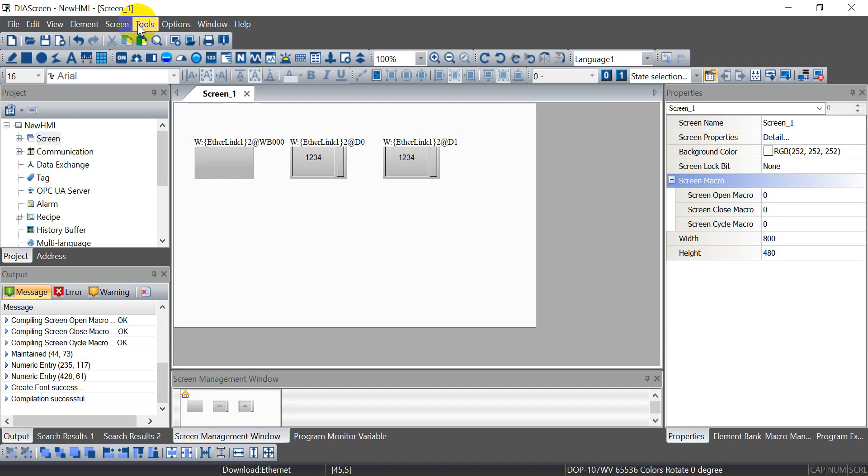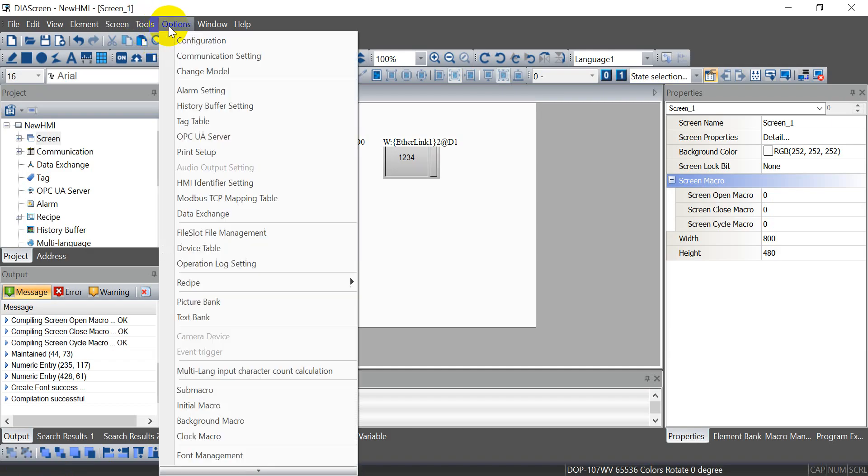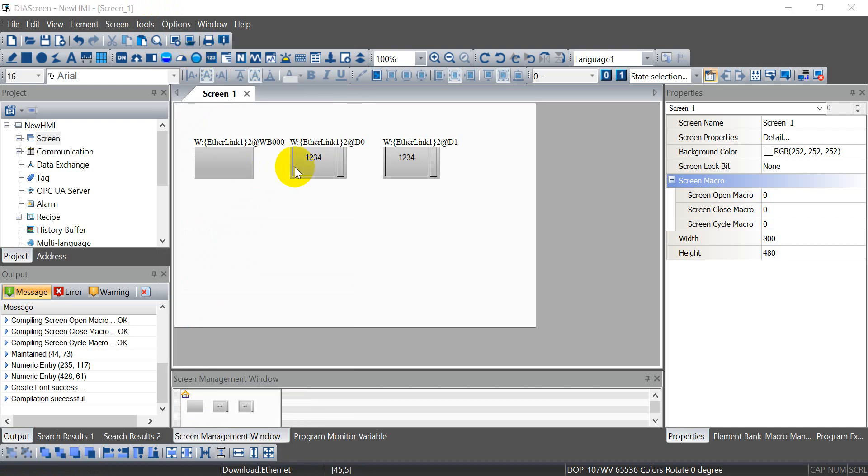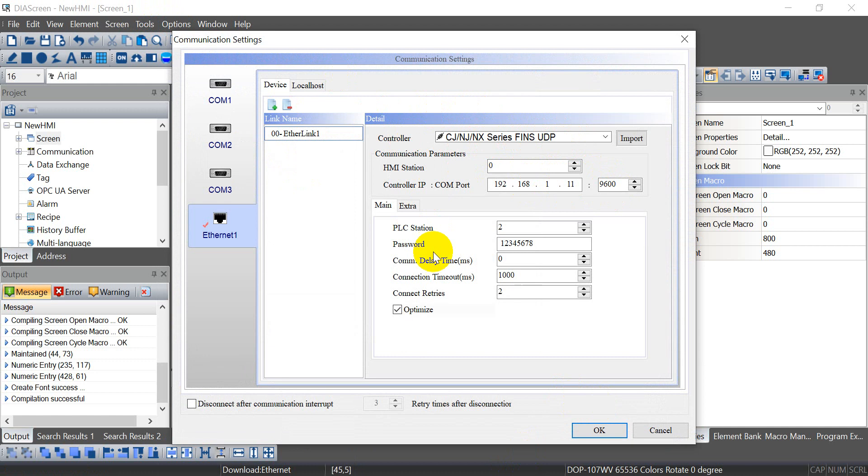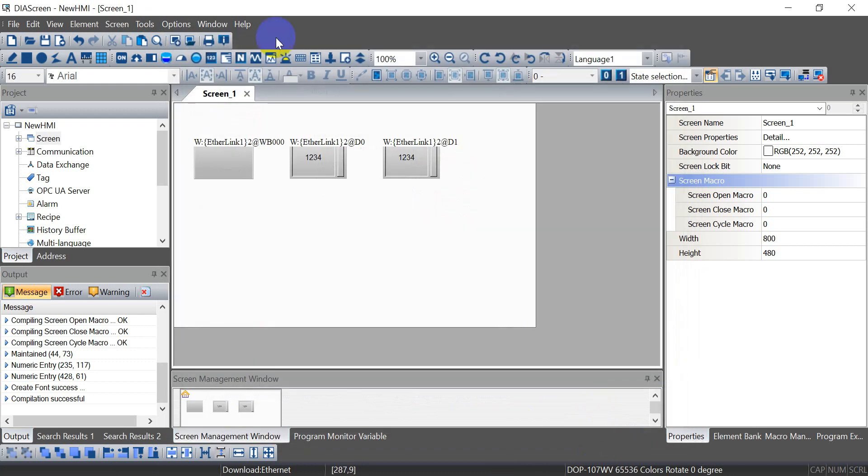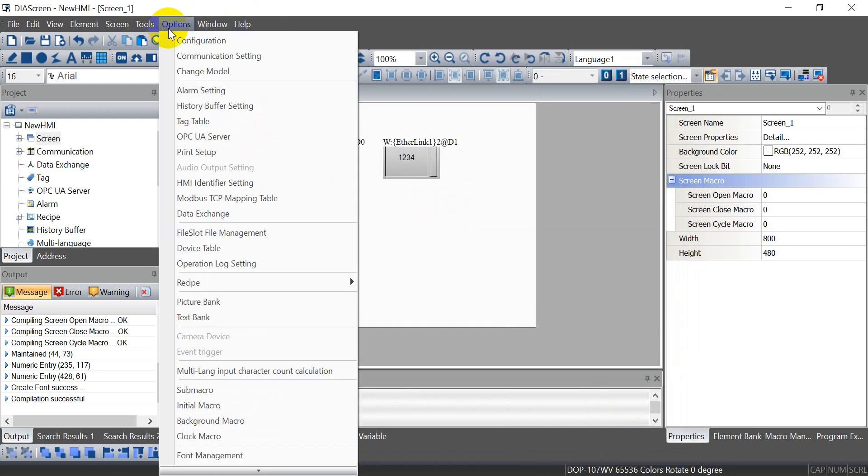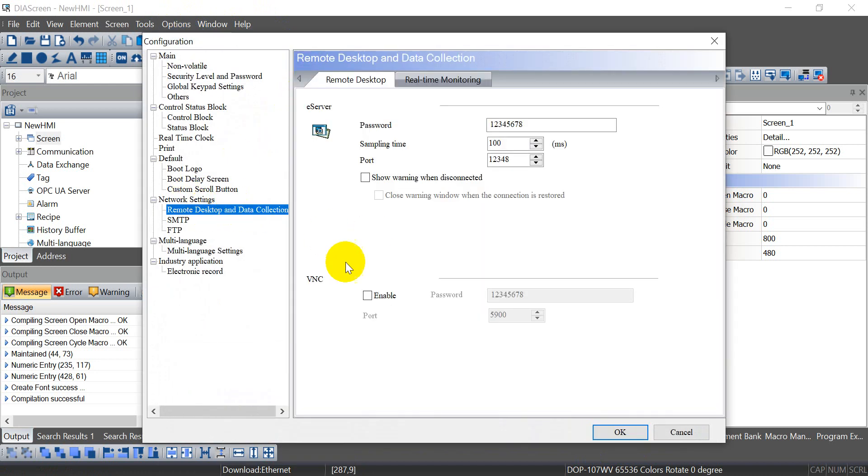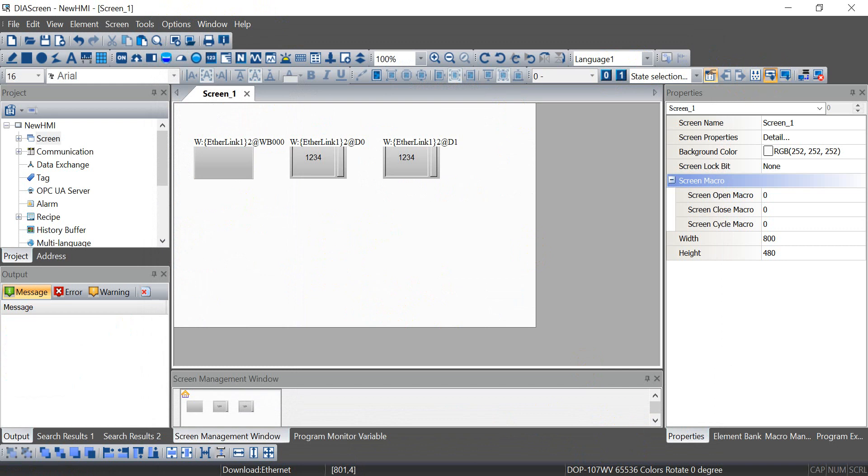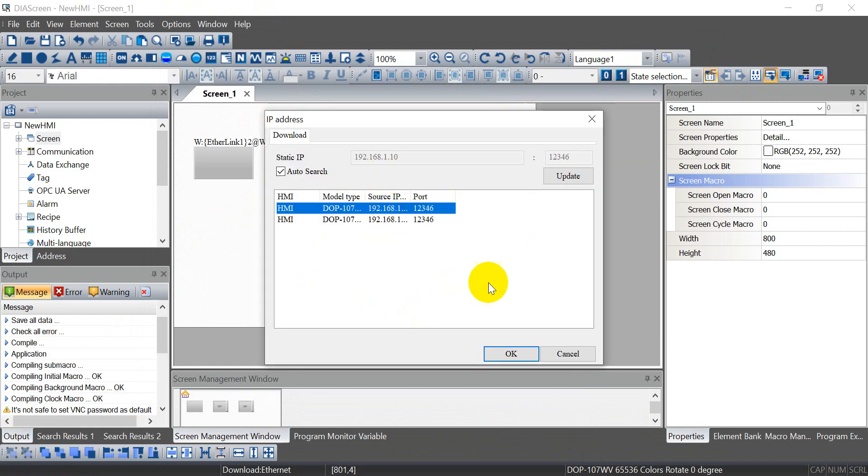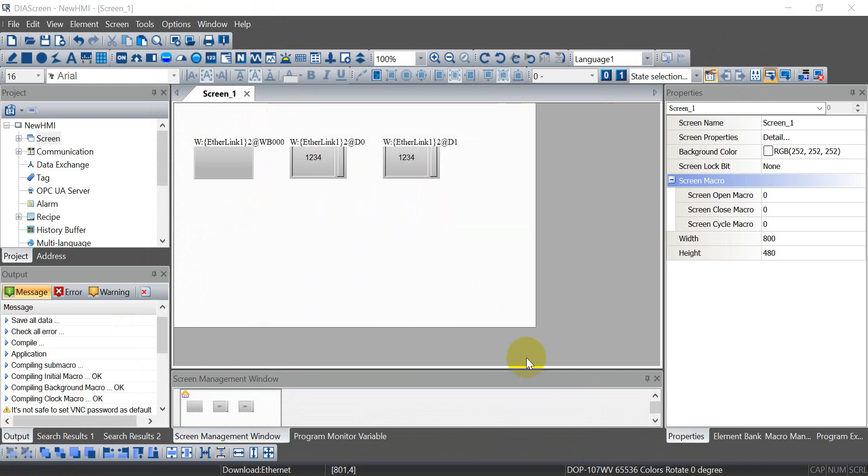Next we will move to the Delta HMI. So you can see the controller type we select NX FINS UDP. And then follow the IP address or port number. And this one we define 192.168.1.10. And because I will show you with the VNC function, remember to enable VNC. And then we can download the program. So click this one and download.